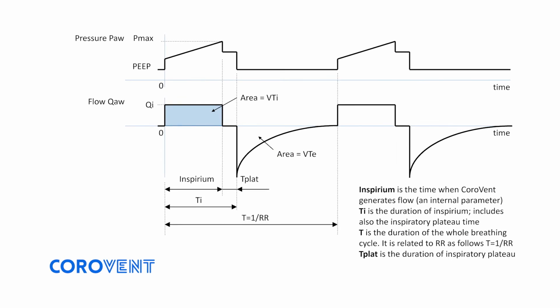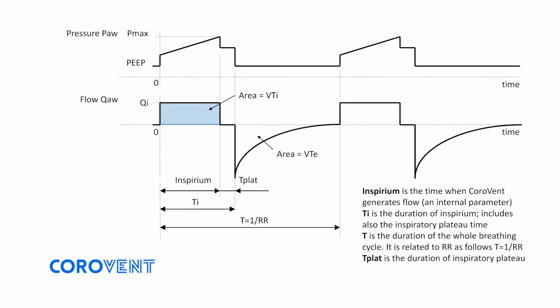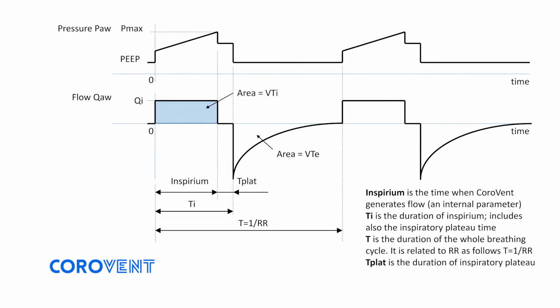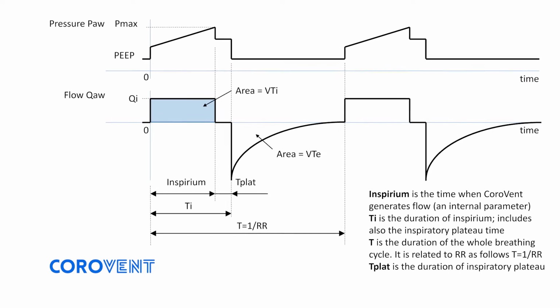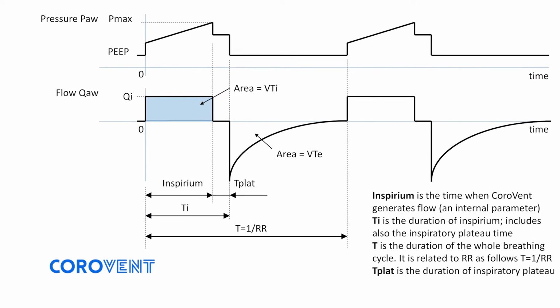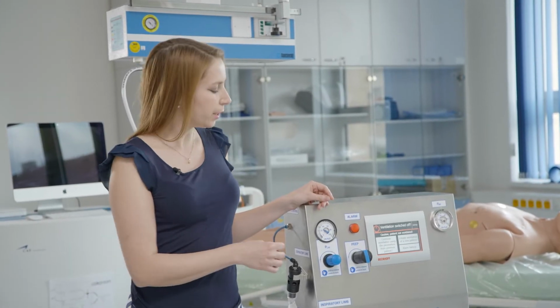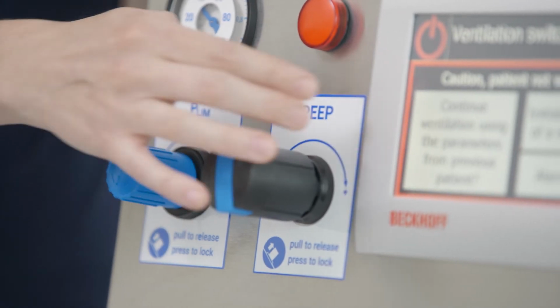CoroVent is equipped with only one ventilation mode, volume control, pressure limited, mandatory ventilation. The ventilator works as a constant flow source in Inspirium. The Expirium is controlled by a pneumatic valve, which maintains the required PEEP and serves as a safety valve and a pressure limitation. The ventilation parameters are set by two rotary knobs and a touchscreen.